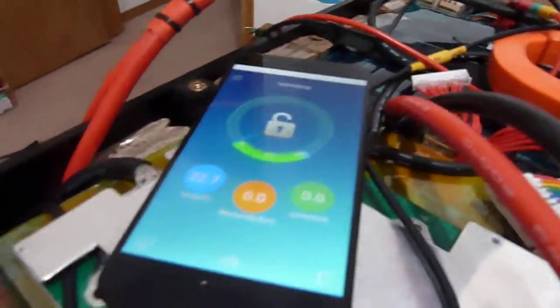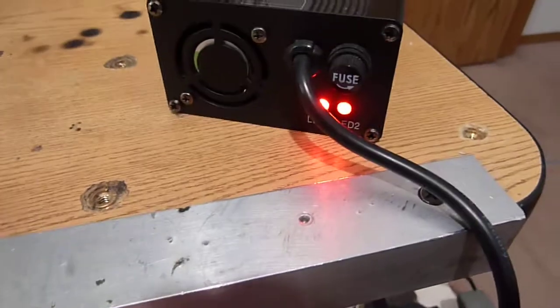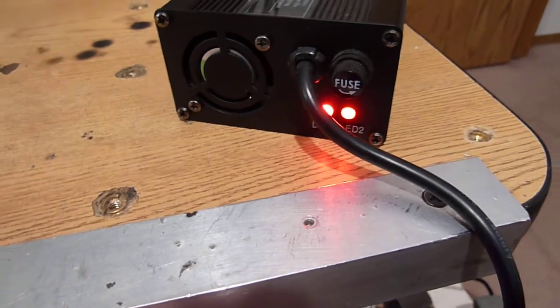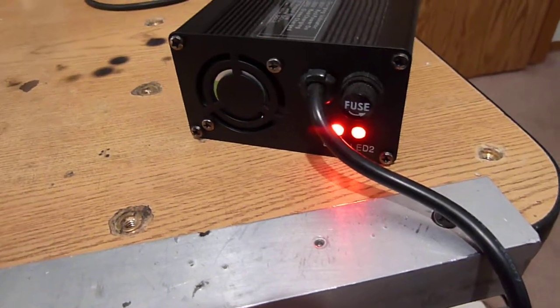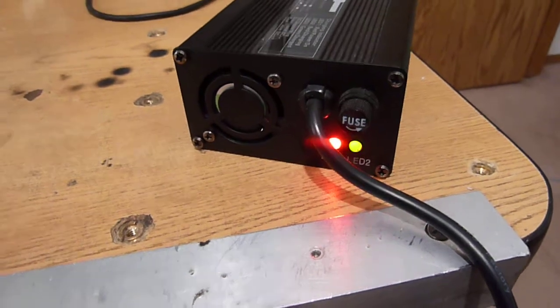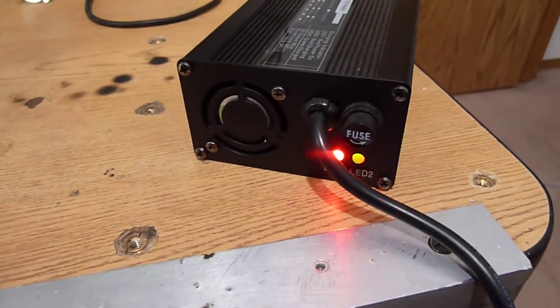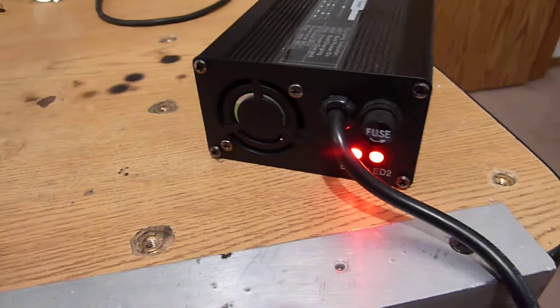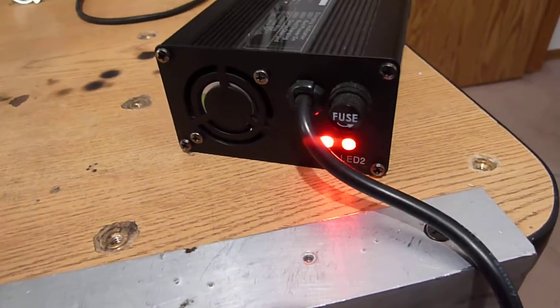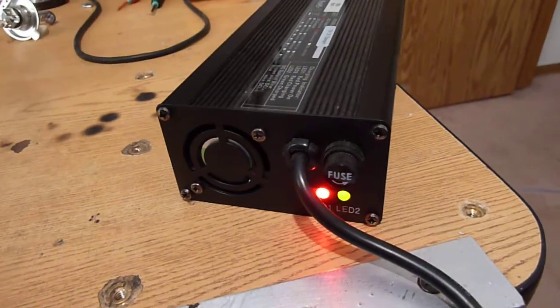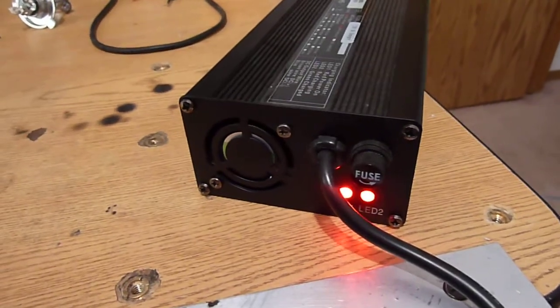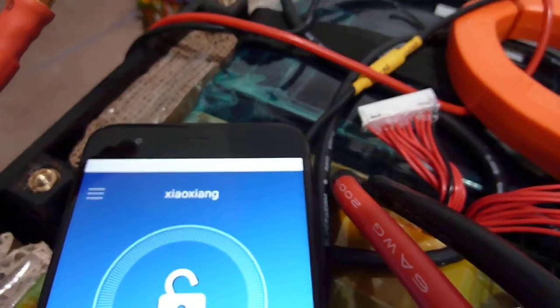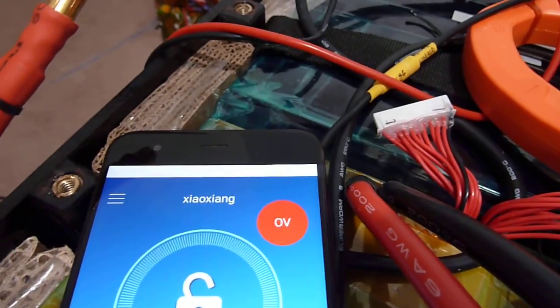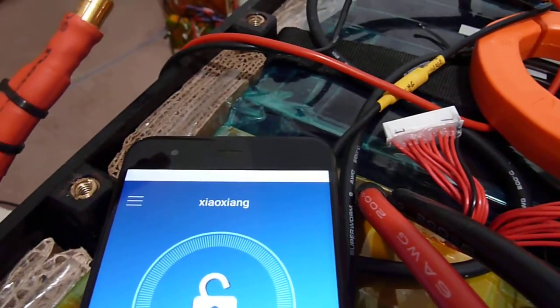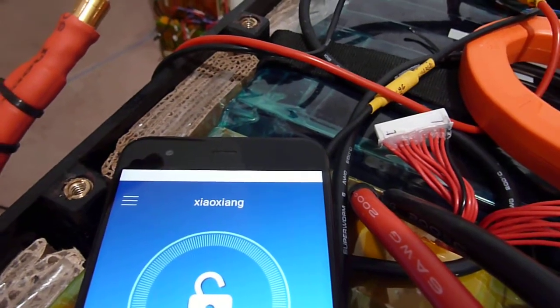But this cycling on and off, like you're seeing here, in the balancing process, I'll see this happen about once every 30 or 40 minutes or so, as the BMS allows charge current in to bring up those low cells, and as the higher voltage cells are balanced down to that lower setting, which is now 4.18 volts. You'll notice up top there's that OV that turns on and off.